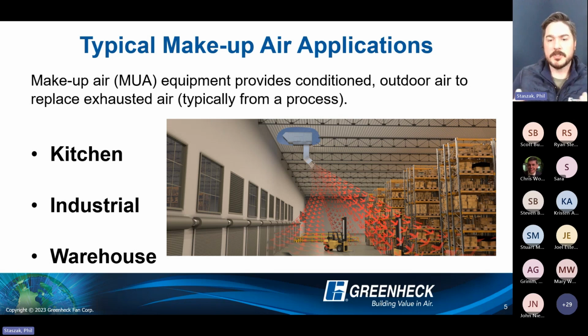But in that building pressure scenario, we can do a recirc unit and provide just the discharge air temperature desired for that space. And then the unit is running constantly, so you're always churning air throughout that facility. The only time you bring in more outside air is when that pressure is lost in the building because a dock door opens up, usually not tied to exhaust systems at all. So general warehouse ventilation is a little different than typical makeup air, but we can utilize the same units to do a dual-purpose unit there.